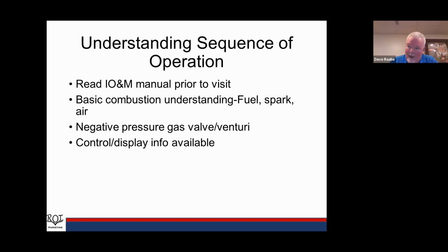If the boiler's running, it will show me my flame signal in microamps. And if I get in to the error screens, it'll show me a history of any lockouts that I've had. So that's going to be valuable information in trying to troubleshoot a problem with a boiler.